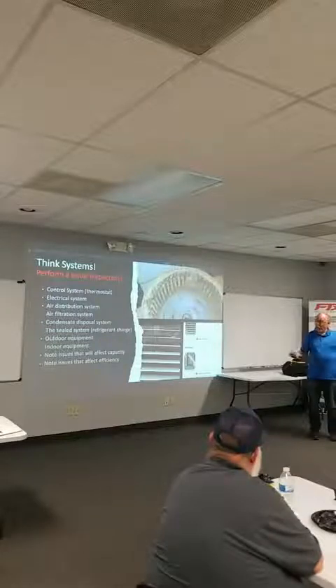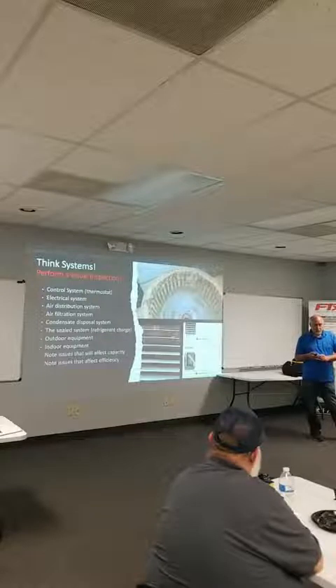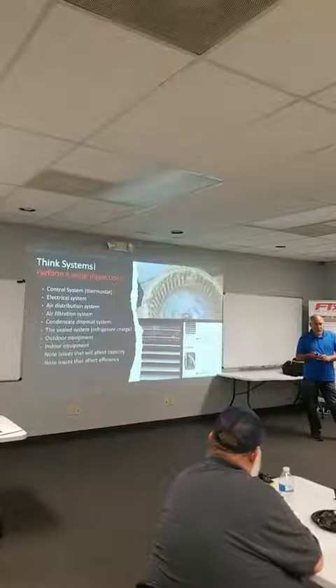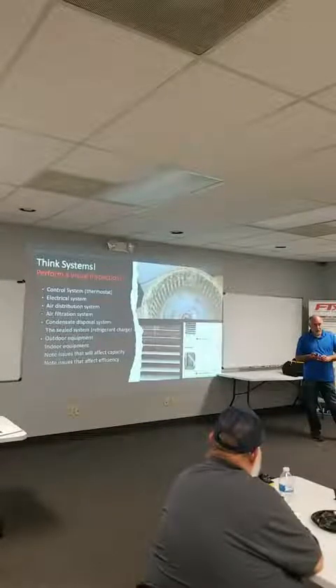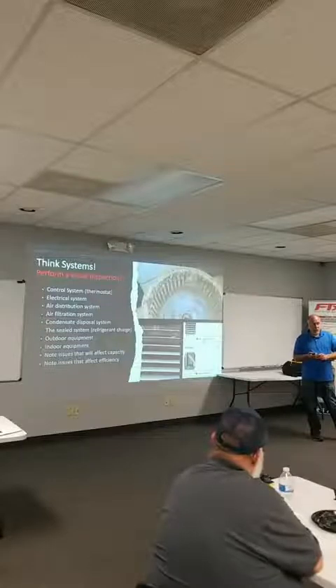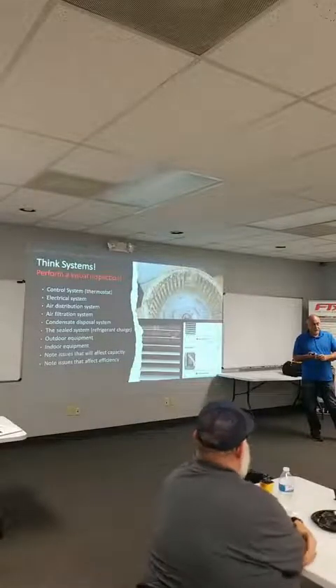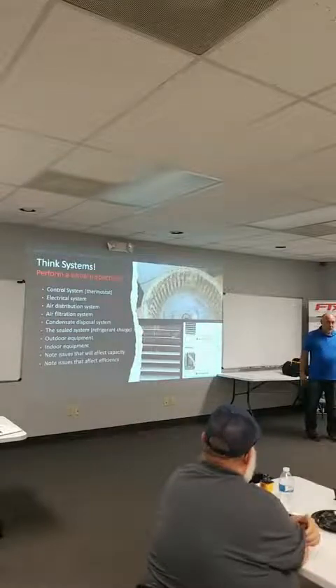But the other thing that we're talking about putting dryers in, I'm a big believer in putting a flare dryer in. I know that you can actually make a flare fitting because I made them, and they work, right? We use them on mini splits, and they can take up to 600 pounds of pressure. A good flare fitting, if you hydrostatic test it, is stronger than a braze, right? Why is a good reason to put a flare fitting on a dryer? So you can change it. So you can actually change it, pump it down and change the thing.